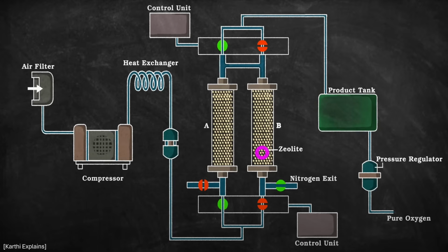Now, in order for the molecular sieve to work, you need to put some pressure behind it, and we'll talk about that in a second. So air is going to come in from the outside and it's going to go through some air filter. Now this is super critical. In fact, there are multiple air filters in a system like this, cascaded, even though here it's only showing one. And you can imagine why. Because these zeolite molecular sieves already have very, very fine porous structures. If any dust or additional particles enter the system, you're going to clog the zeolite, and then there's no way to clean it out. You're going to have to throw it away. So filtering the air before the next step is really important.